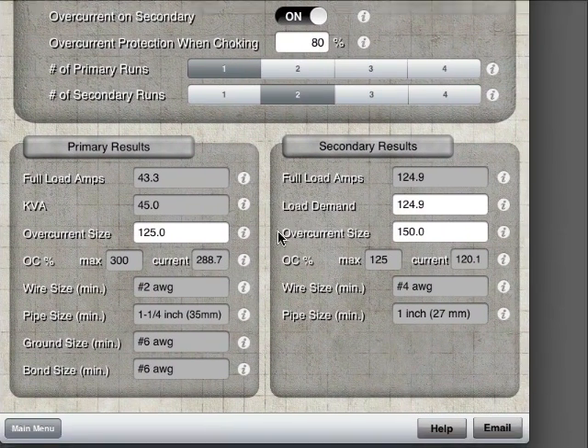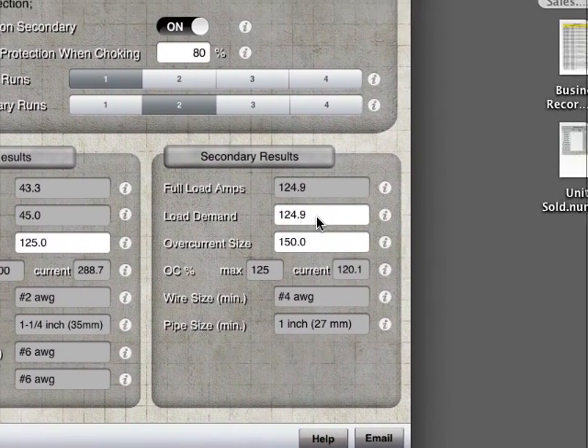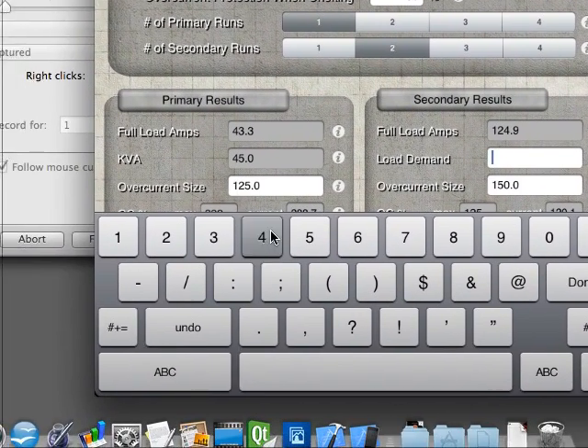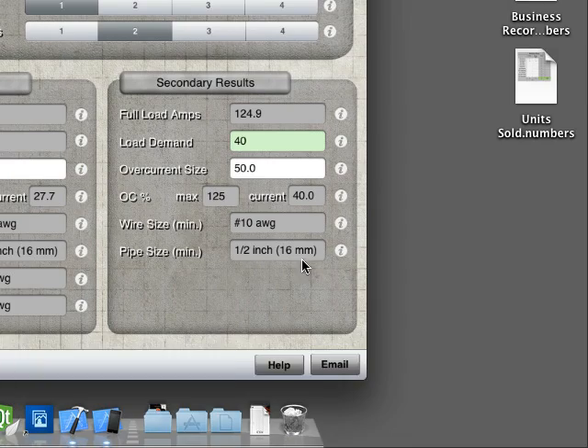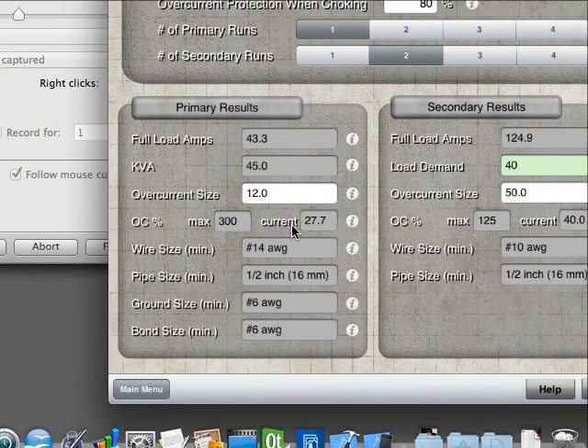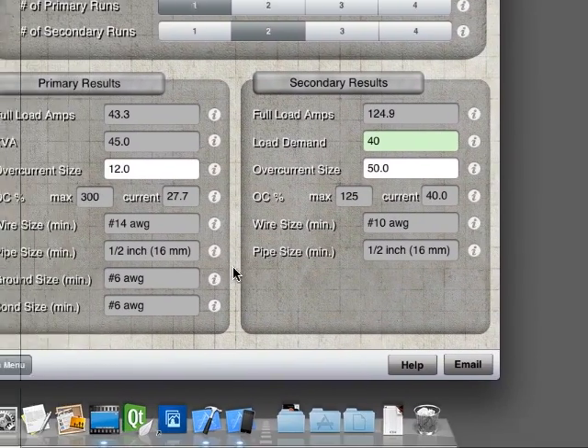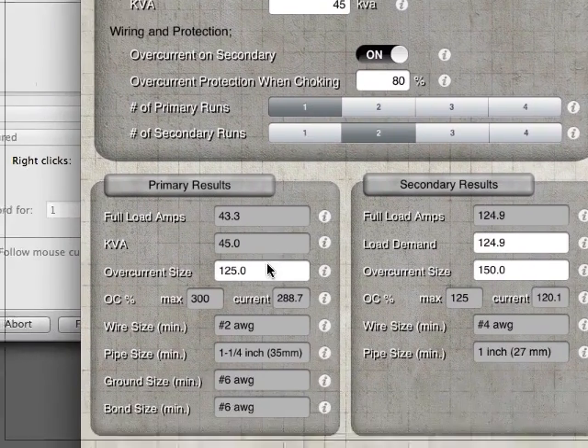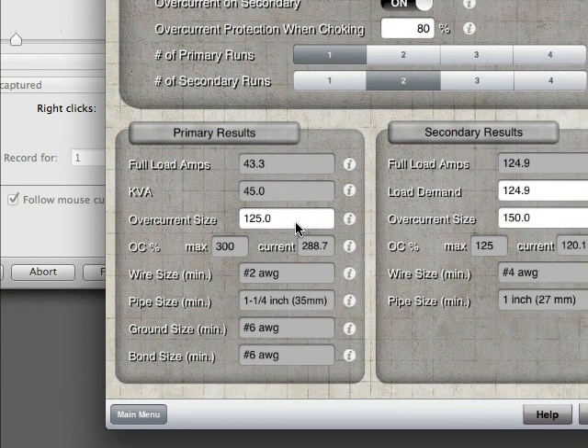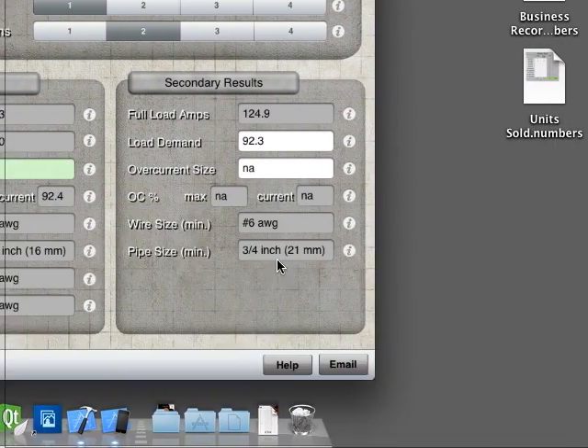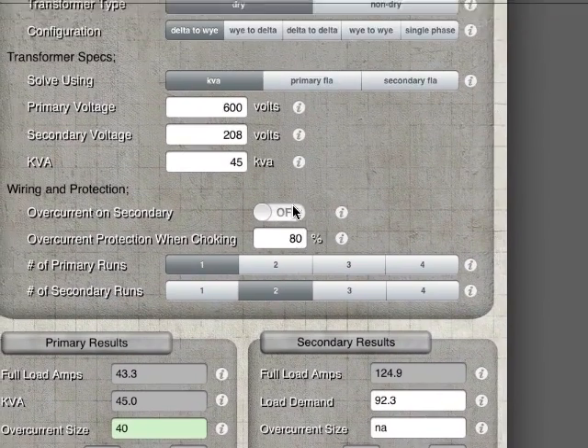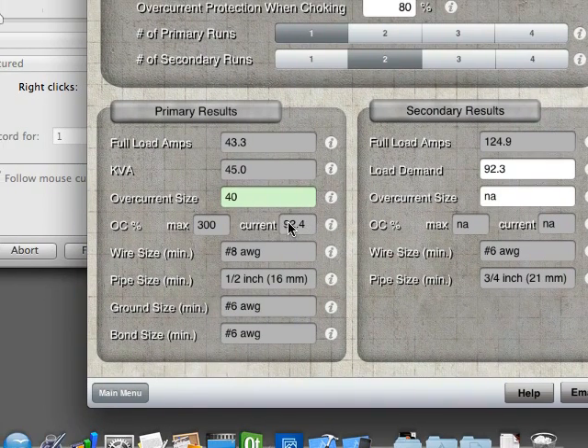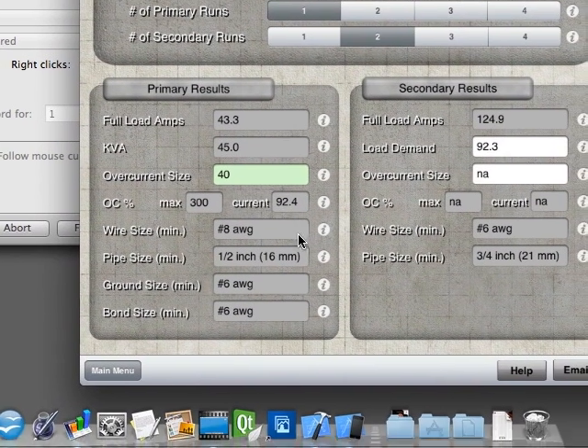Now once you have it set in here, you can tweak some values. So if you want to choke down your transformer, say your load demand is only 40 amps, you can tweak this down to 40 amps. And as soon as you hit done, it will give you your new overcurrent sizes, your new overcurrent percentages, and it will keep everything within spec. And as soon as you change up here again, it will reset everything. So, let's just do for an example, because if you put this overcurrent size down, choke it down to below 125%, you'll see the secondary overcurrent protection will turn off, because it's not required if your primary protection is under 125%, and ours is set at 92.4. So we're fine there.